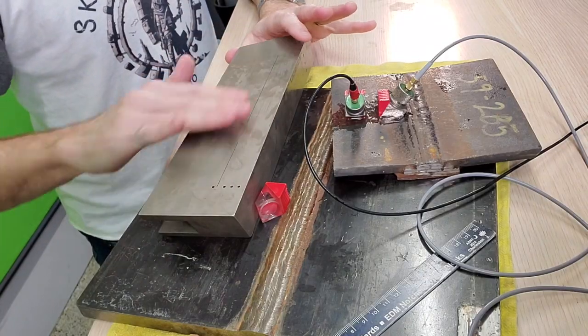What I'm talking about overall here is the surface finish on your sensitivity calibration block that you would use for weld inspection. If you have things like an IIW beam profile block, or even just a simple step wedge, it's fine for those to have nice shiny surfaces on them because we're not using them to set amplitude for weld inspection. Now, the surface finish on this is dull.